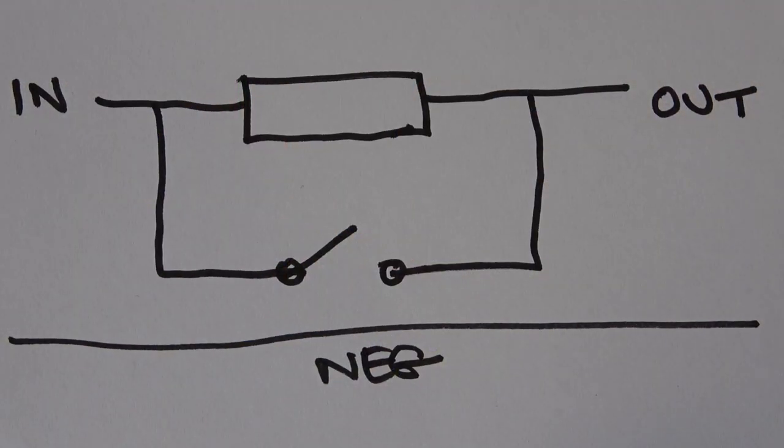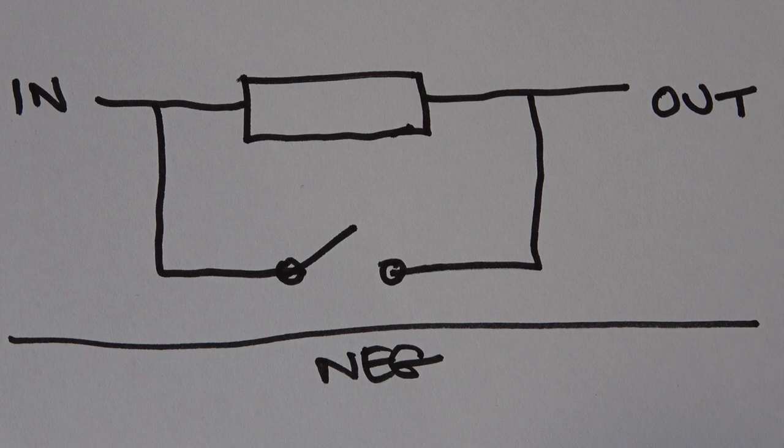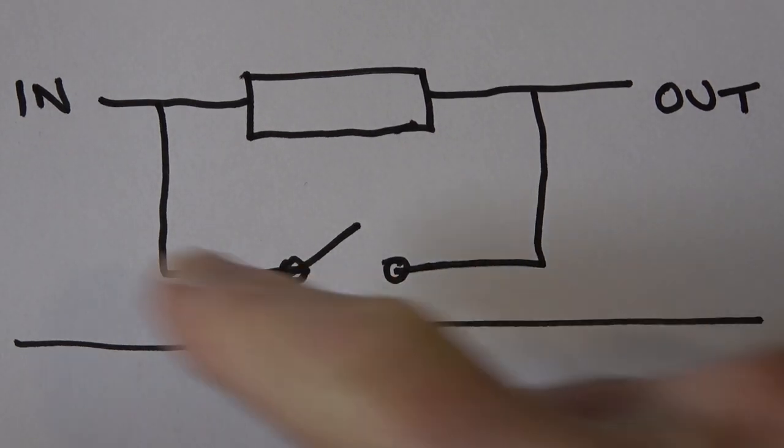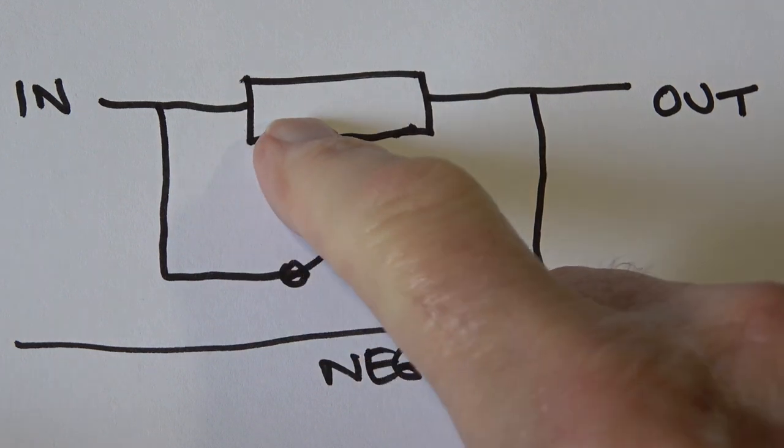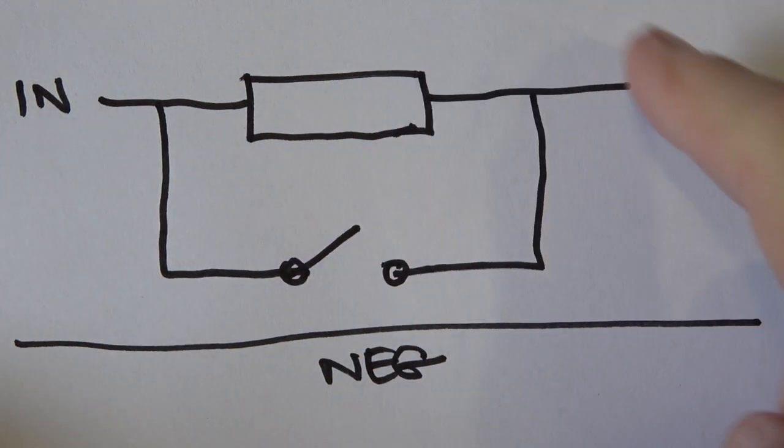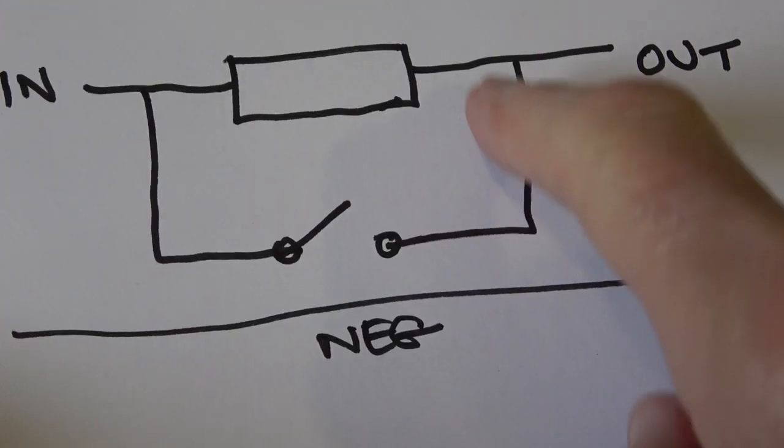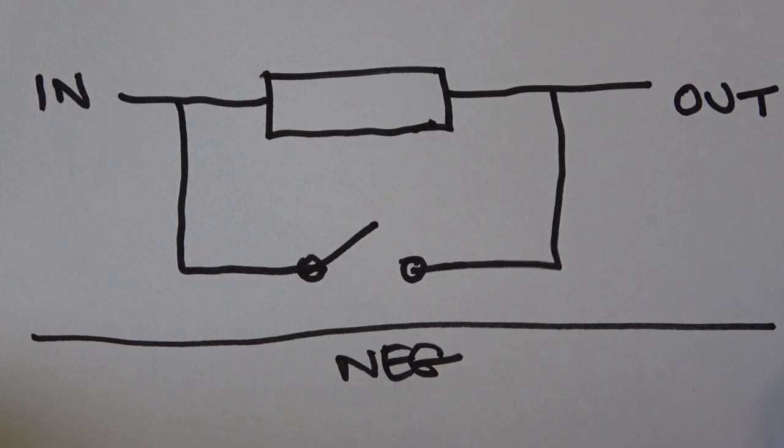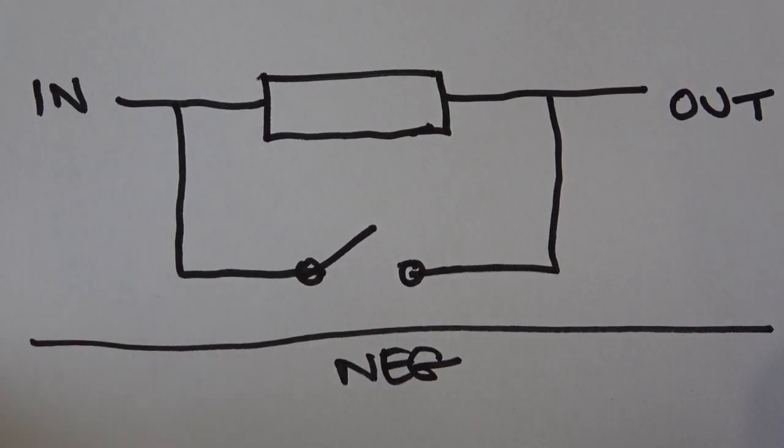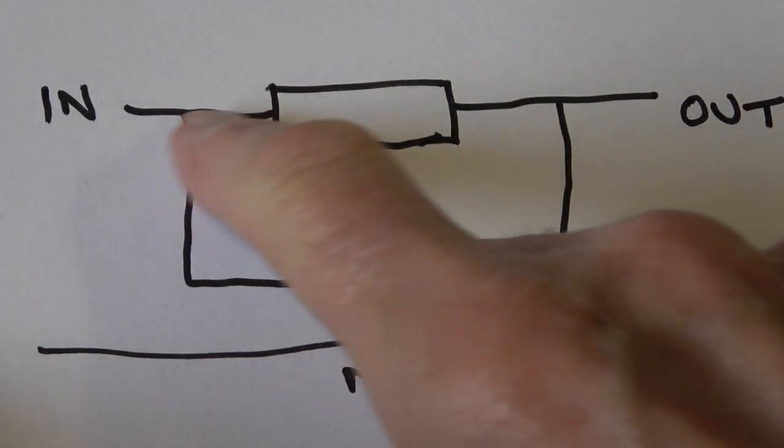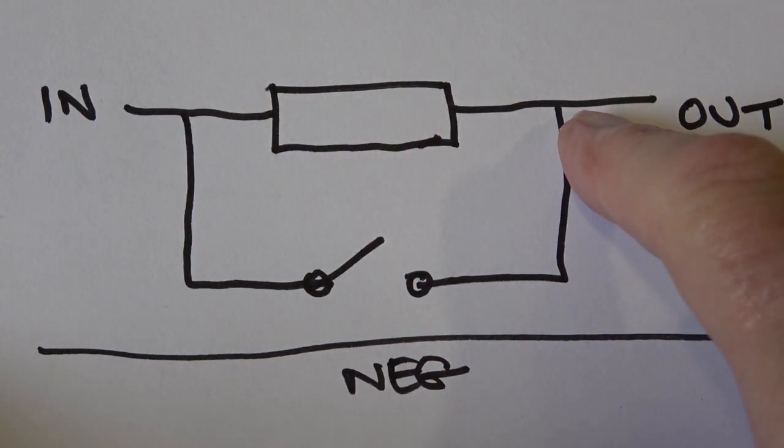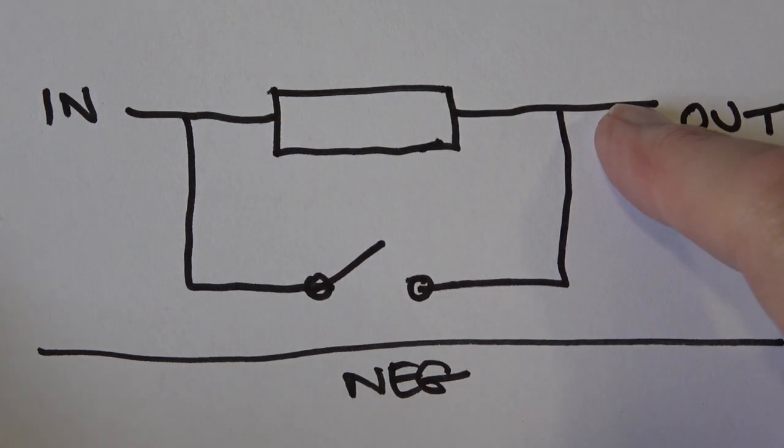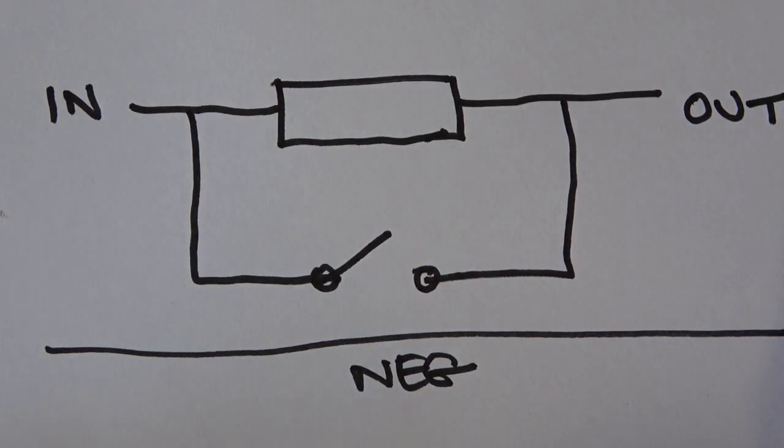This represents a very crude drawing of a surge limiter or current limiter. The mains power goes in here, there is a resistor here, and there's a switch across the resistor. The idea being when the power first comes on, this resistor is in circuit and limits the current that is capable of being drawn by the transformer.